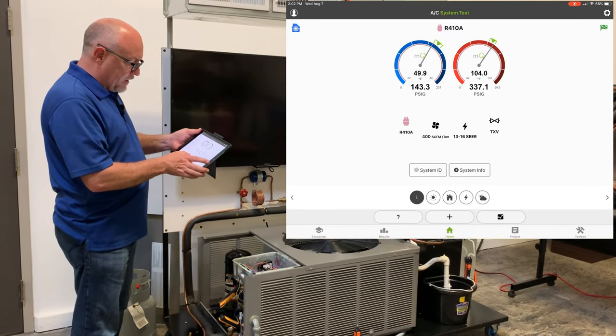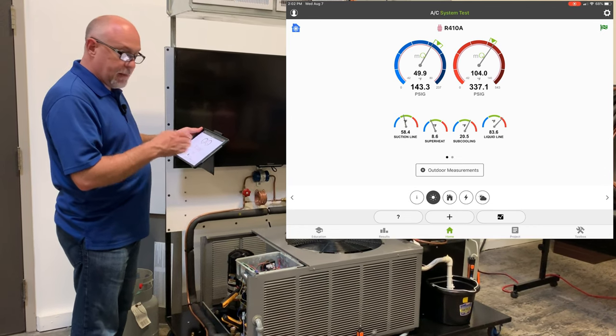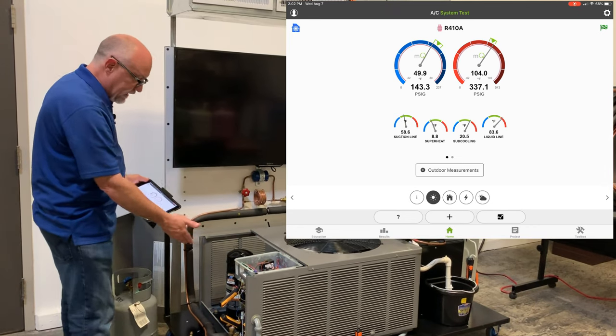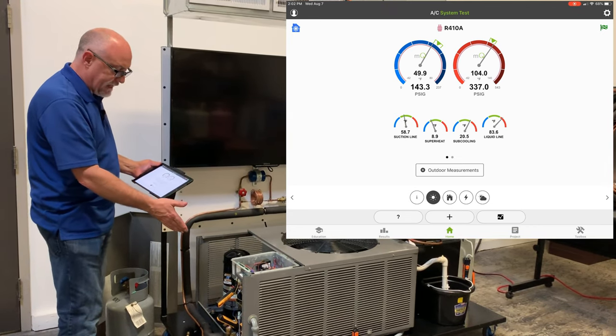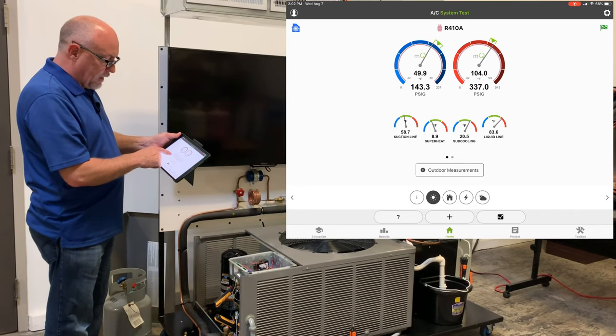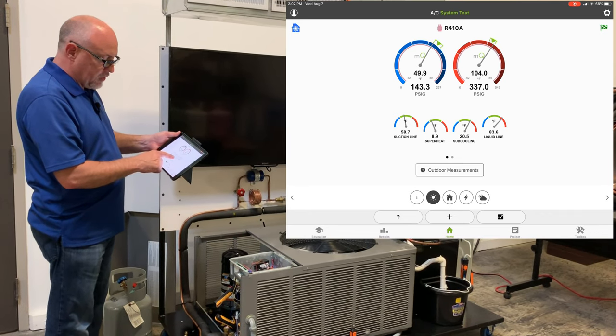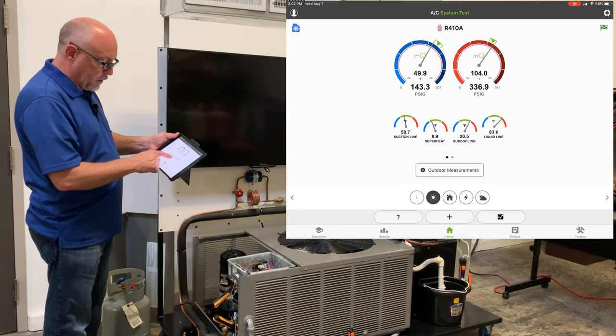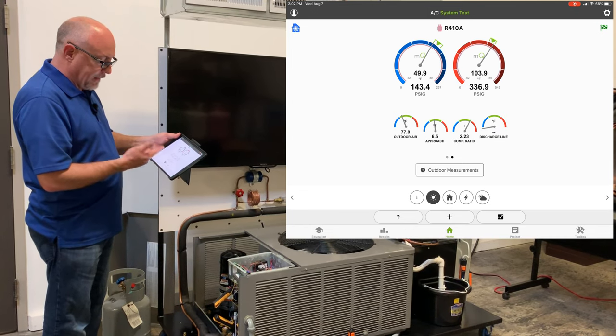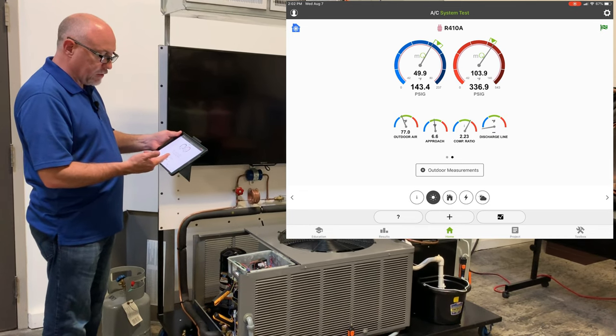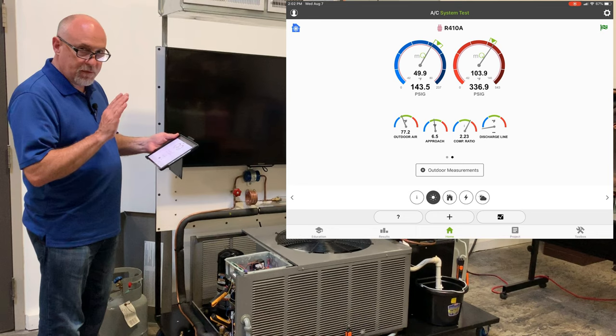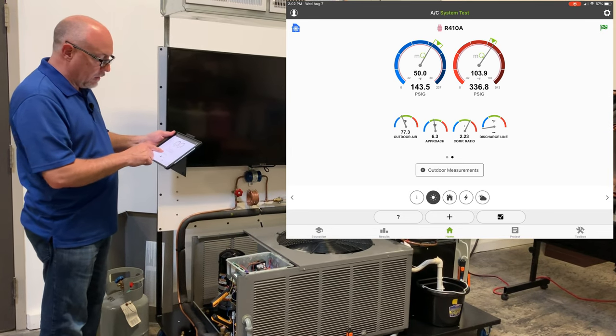Now we get into the sunshine, the next button over, that's all the measurements that we typically take outdoors here at the condensers. If I click on that the first time I'll see my suction line, my superheat, my subcooling liquid line. Tap on it again I'll see my outdoor air, my approach, my compression ratio. But in this case you'll notice I have nothing on here for discharge line at all.